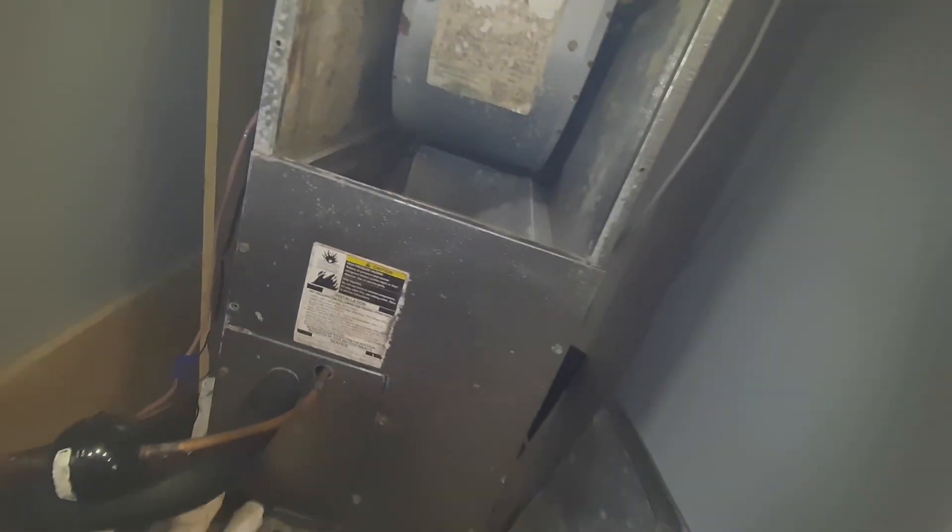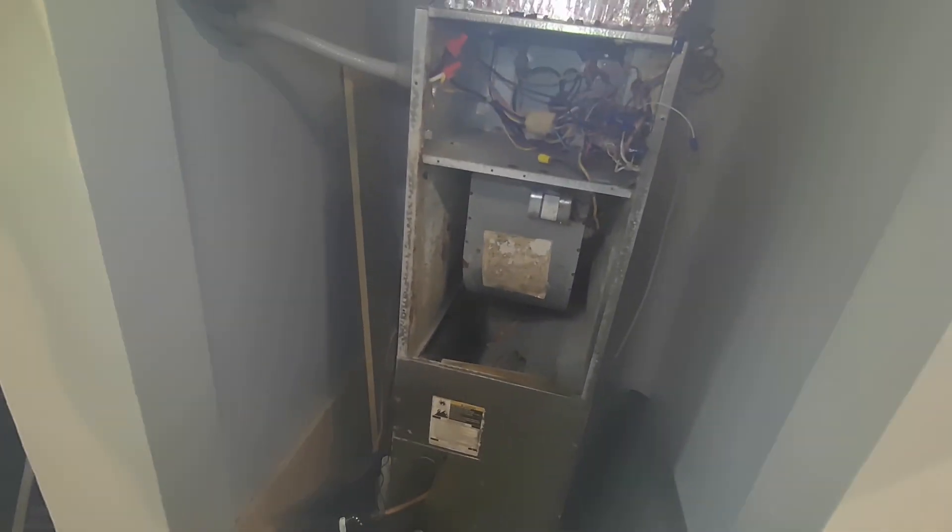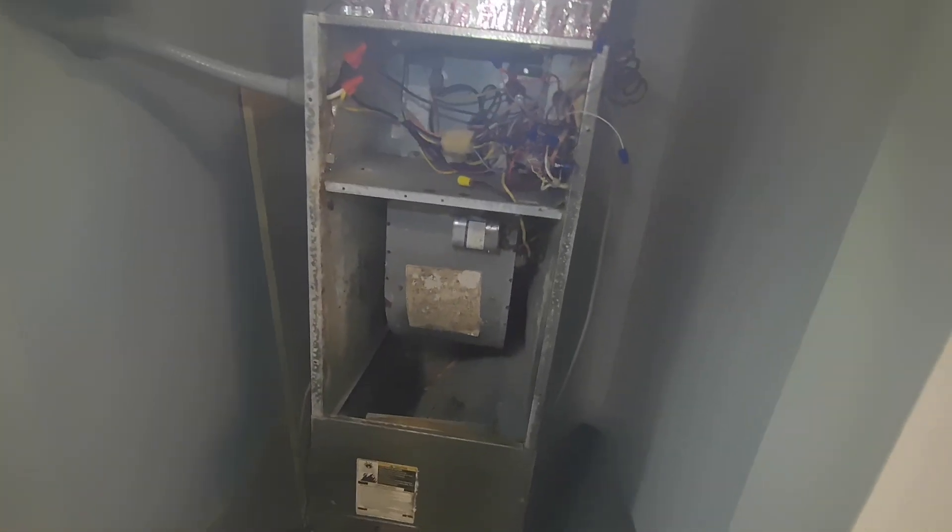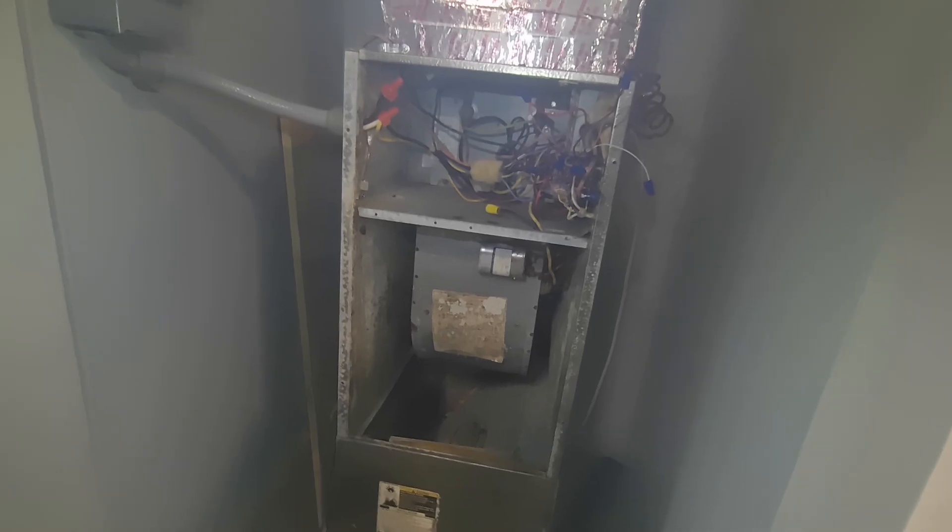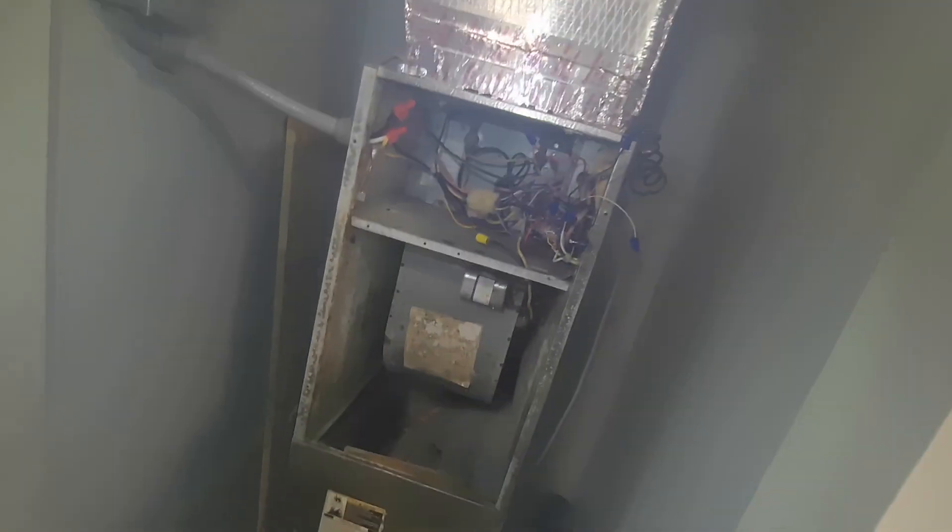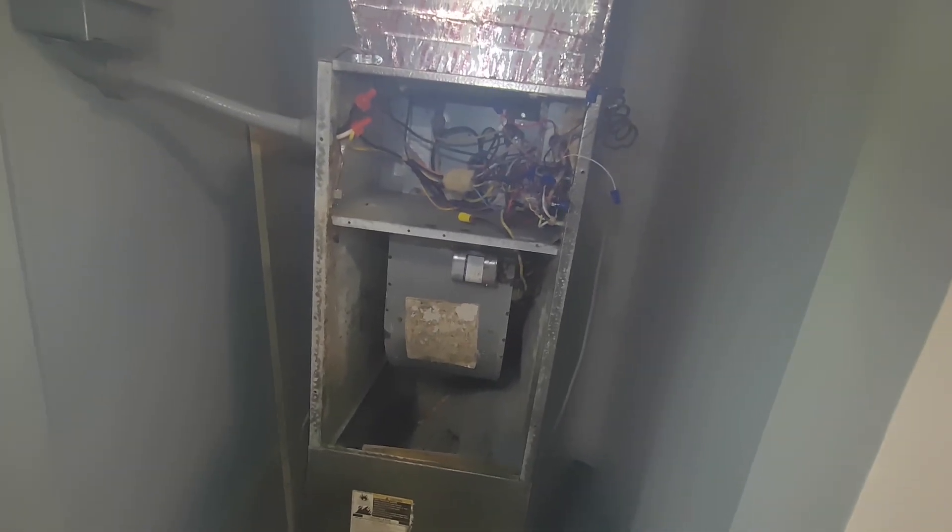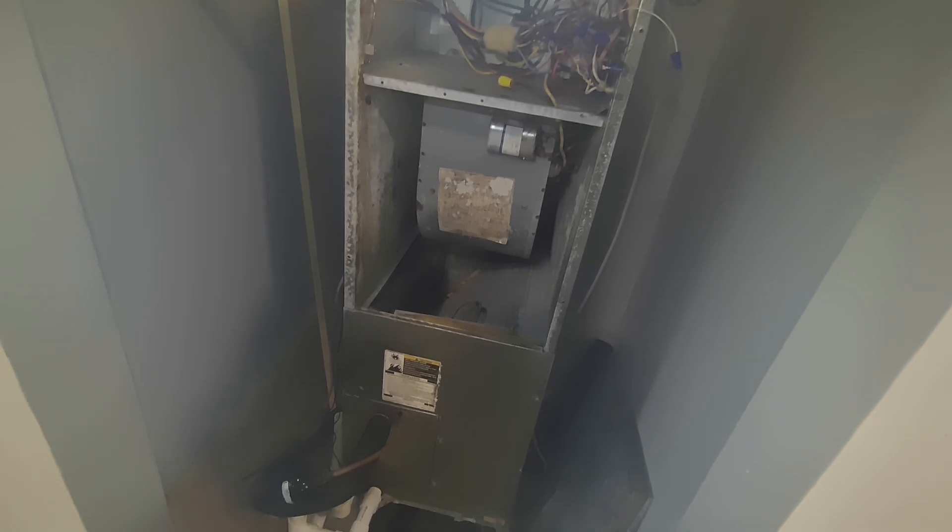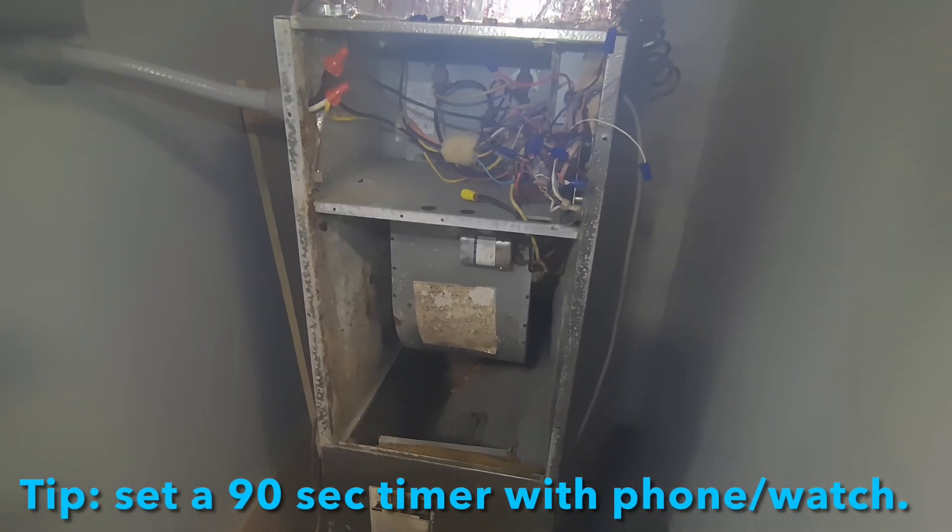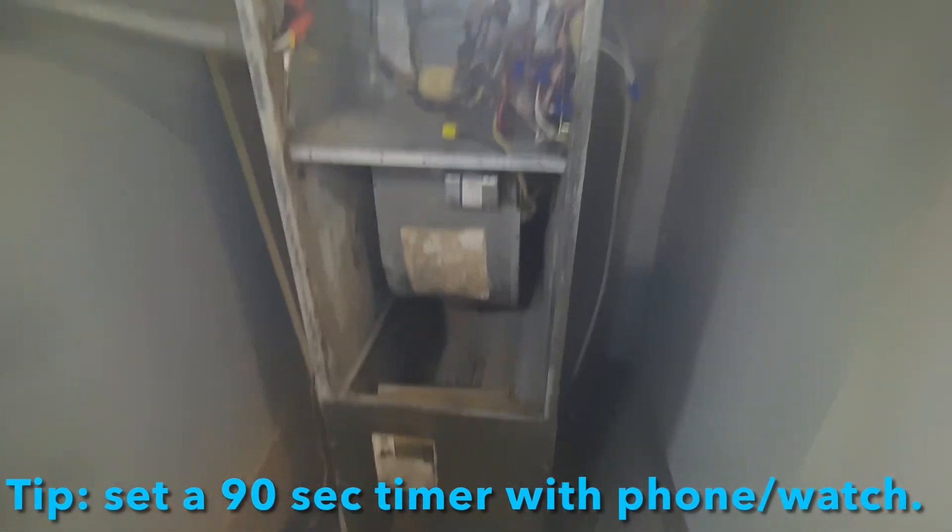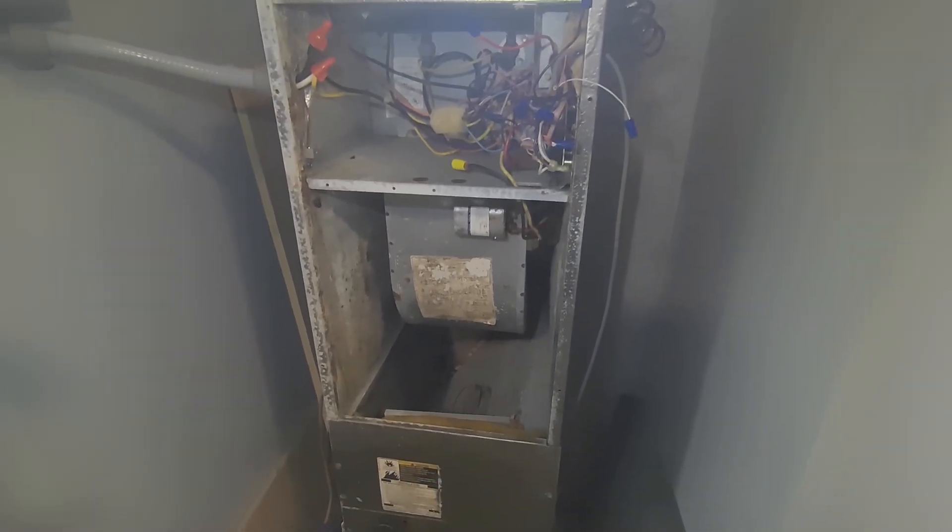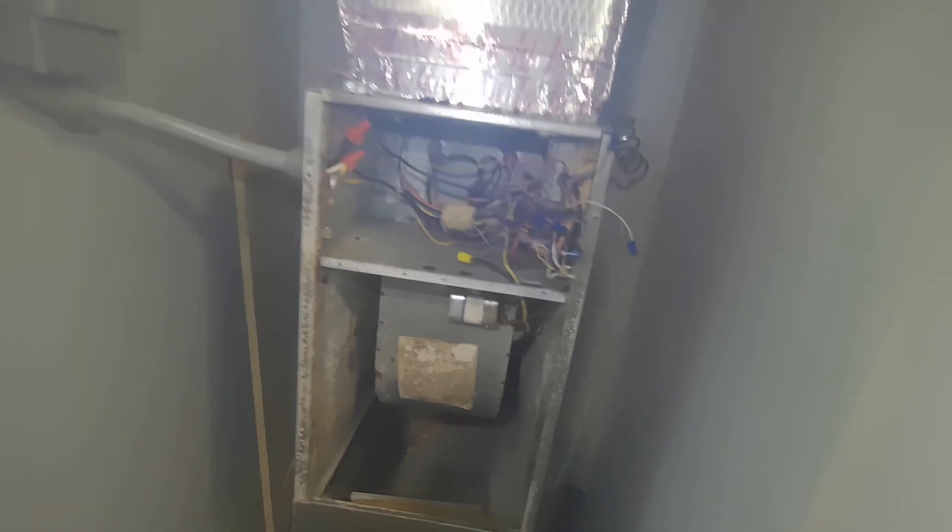Do keep in mind that some of these units do take about 90 seconds to turn off, so don't feel like after you've pressed it and it's not turning off that something's wrong. Just give it some time and it'll turn off. So let's wait a little bit. There you go, so usually it does take about 90 seconds and that means that is off, even though we have our thermostat calling for the fan to be on.